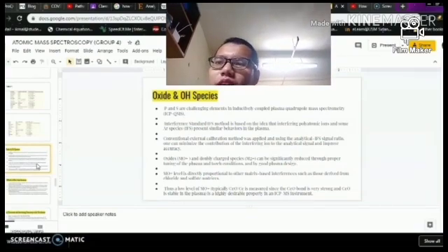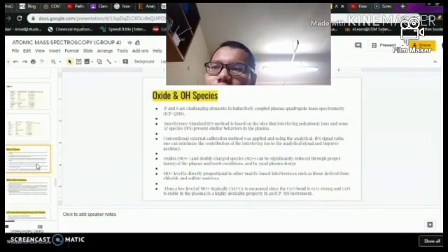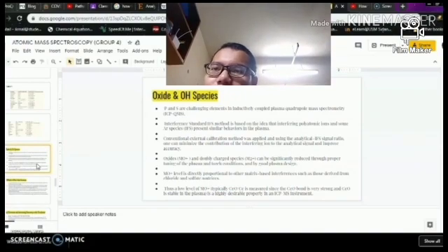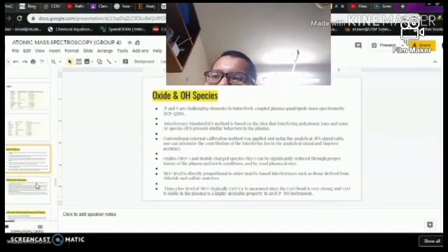Thus a low level of MO plus, typically CeO, is measured since the CeO bond is very strong and CeO is stable in the plasma, and it's a highly desirable property in an ICP-MS instrument.